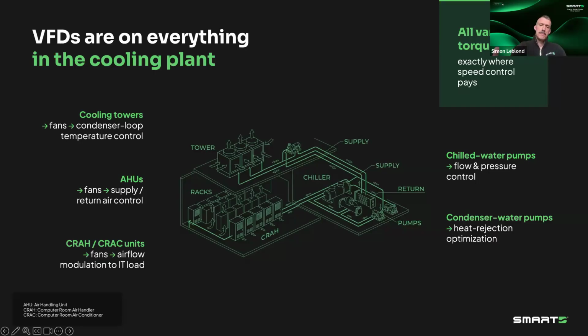So, if you've got a rough number, 10 megawatt facility, you're running 30 to 50 VFDs. Anywhere between 10 and 60 horsepower. If you don't have a harmonic strategy and you aggregate all of those harmonics together, your total harmonic distortion at the point of common coupling can reach 20 to 40%. So you're not compliant, but you're also going to have impact in your facility. The limit mandated by IEEE 519 is below 5%. So you're 4 to 8 times higher than what you should be. And that's really why you need to think about it before the design, not as an afterthought.